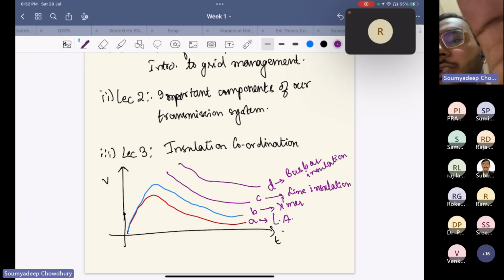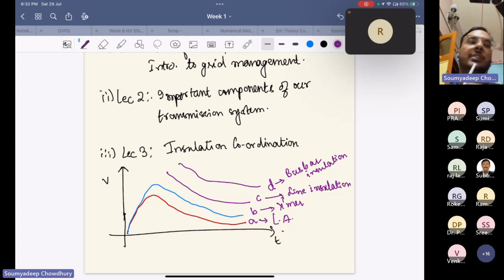So if any over voltage comes, we are designing the basic insulation level of different equipment such that it attacks the lightning arrestor first and the current is dissipated. It will not further attack the transformer, because the breakdown voltage of the basic insulation level provided to the transformer, line insulation and busbar insulation is much higher than the lightning arrestor. So whenever a high voltage comes, it will first attack the lightning arrestor and the current will get dissipated. This is in brief the idea of insulation coordination.